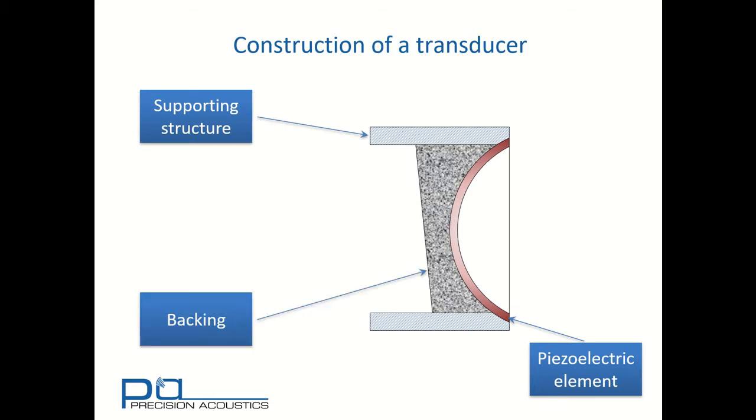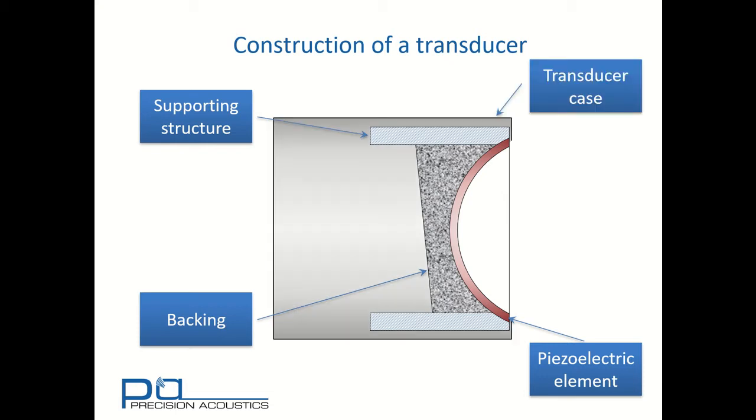Let's look at the construction of a basic transducer. We start off with a piezoelectric element. In this case, I've shown a spherically focused one. There'll be some form of supporting structure and some form of backing to the transducer. This will all be within some form of a transducer case and may well have a matching layer to help adjust the acoustic impedance on the front surface.